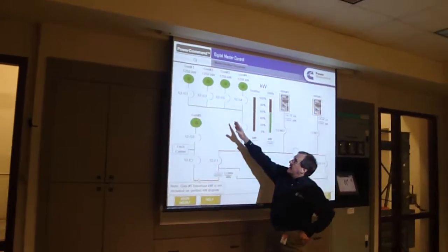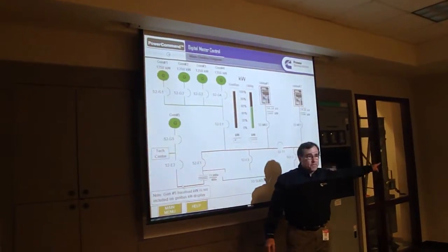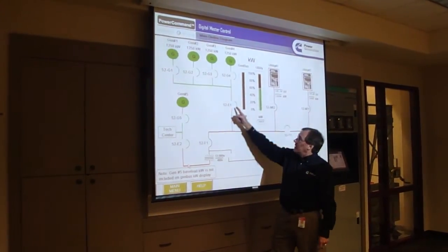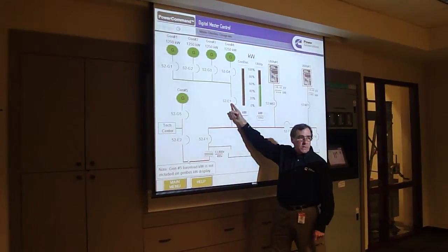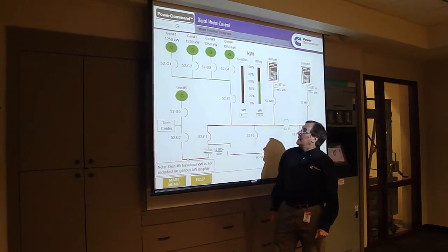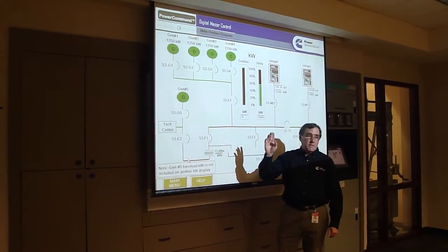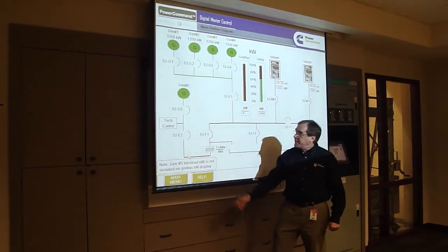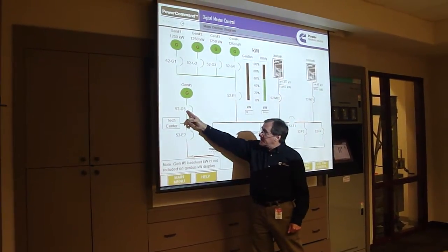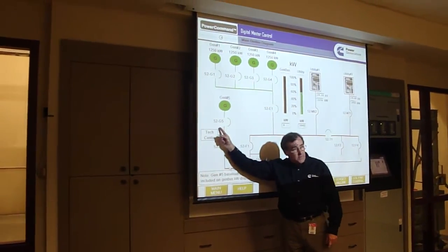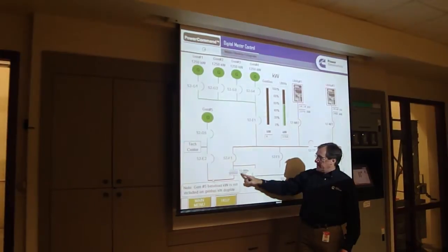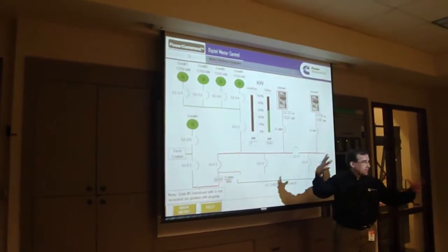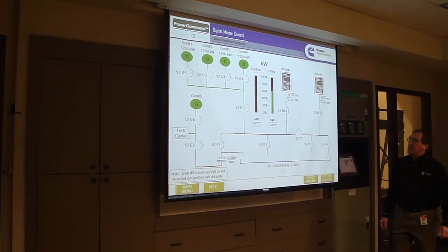Over here, you have the four generators that are in this room right here, and the four breakers that are in the room behind me. In the utility room on the other side is this generator main breaker. Another generator exists at our technical center across the parking lot — our tech center — and that one stands here and feeds our tech center at 480 volts. But then we feed it back in and tie it through a transformer back into our main bus so that all these generators can operate together on the same bus in any combination we need.